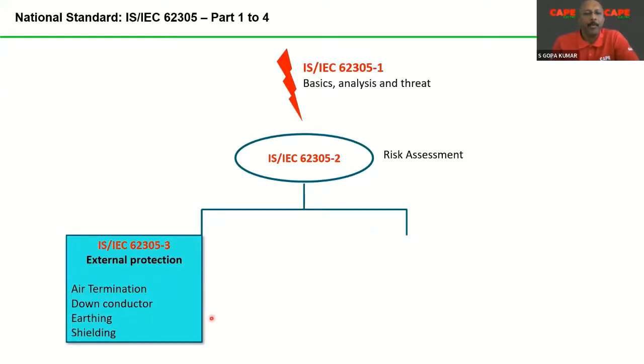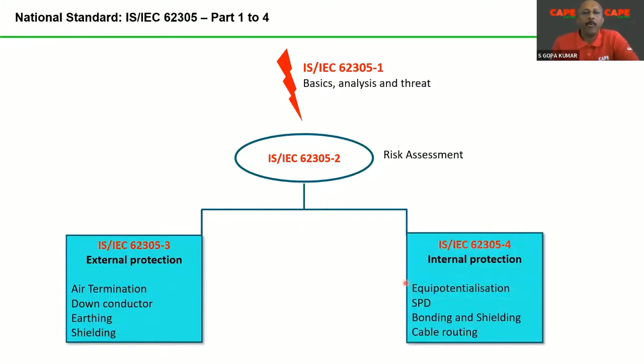Part 3 talks about external lightning protection. External lightning protection consists of air termination, down conductor, earthing, and shielding. Air termination at the top of the building: how you are avoiding a direct lightning strike into the building. Second one, how safely you are carrying the lightning current from top to bottom of the building. The third one, earthing: how safely you are dissipating the current to earth. Shielding: how safely you are avoiding some kind of sparkovers and so on. Part 4 talks about protecting the internal parts of the building. Here the subjects are equipotential bonding, surge protective device, bonding and shielding, cable routing, and so on.